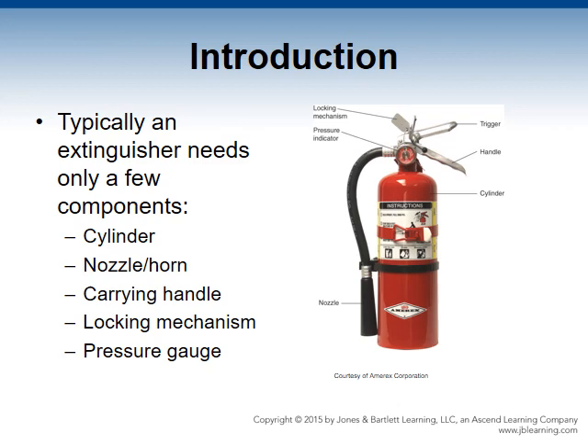Typical extinguishers need only a few components: a cylinder, a discharge nozzle and hose or discharge horn, a discharge trigger, a locking mechanism, a carrying handle, and a pressure gauge. The cylinder holds the suppression agent, which is released when the trigger is activated. The nozzle or horn directs the agent onto the fire. The carrying handle makes it easier to move. The locking mechanism, traditionally a pin inserted into the trigger, prevents accidental discharge. The pressure gauge indicates if there is sufficient pressure to discharge the agent.